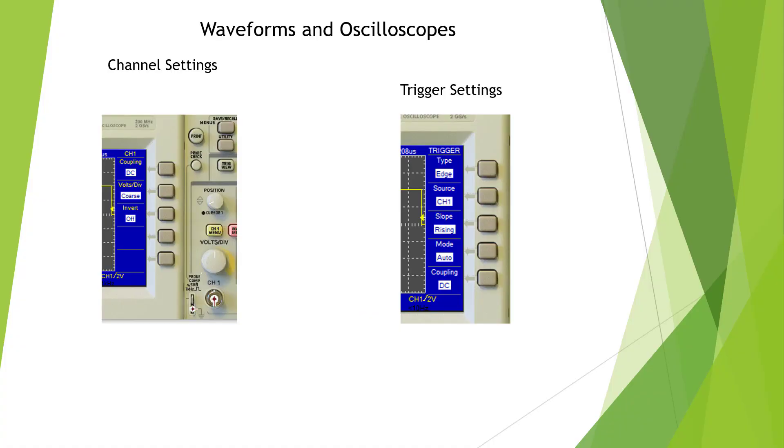Here I'm showing some basic setup. We need to go to channel 1 menu or whichever channel we're using. Push this. And we need to use DC coupling, coarse, and leave invert off. There's a fine setting but you have to turn the knob to get the voltage we need. AC coupling puts a capacitor in line and it will block out all the AC. It's probably okay for what we're doing most of the time but it's best to leave it at DC. If you turn invert on, it will completely invert the signal. Plus will be minus and vice versa. Here we have trigger settings. We need to use edge, the channel we are, rising or falling depending. And mode auto will be fine. Coupling DC and we need to make sure that our arrow is touching the waveform.